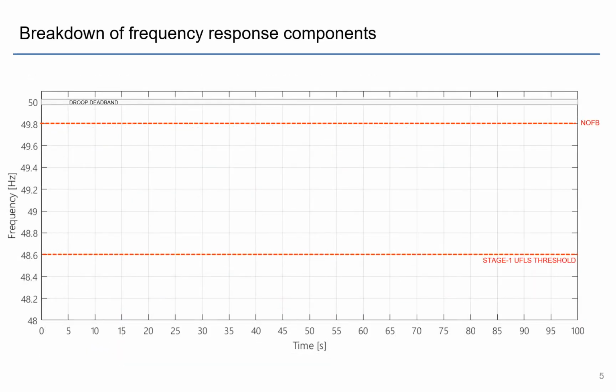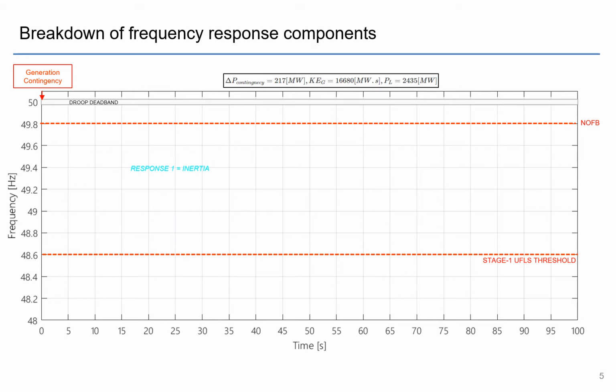Here we break down the frequency response components and tease out what they do and the effect they have on system frequency. So here we have a generator contingency. In this case, this is actually a real contingency as well, so 217 megawatts, and the generator inertia at the time was around 16,680 megawatt seconds and a load of 2,400 megawatts. And if all we had was inertia, this is what would happen.